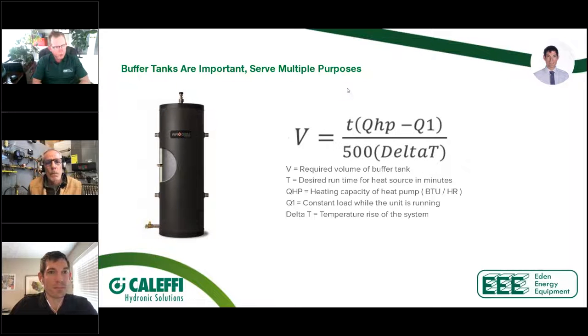Max, again, we have a whole module on buffer tanks. We just want to quickly talk about the purpose of the buffer tank. Yeah, so another thing to look at with the formula here is there are different buffer tank formulas depending on the heat source that you're tying to it. So if it's a modulating boiler that's going to go down to, you know, a 10-to-1 turndown or something like that, you're going to use a different formula than you would for an on-off heat source or something like an old high-low boiler or something like that. So make sure that you're grabbing the right buffer tank formula. This is something that buffer tank manufacturers will be able to help you out with little calculators that will give the right version of this math there.